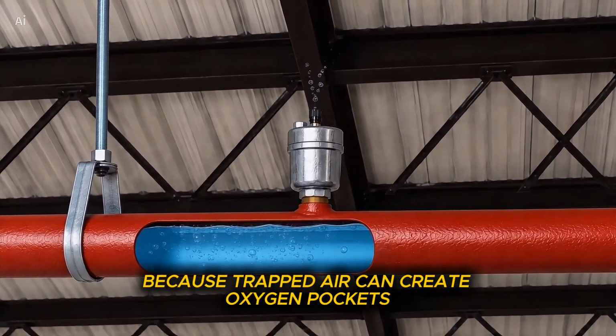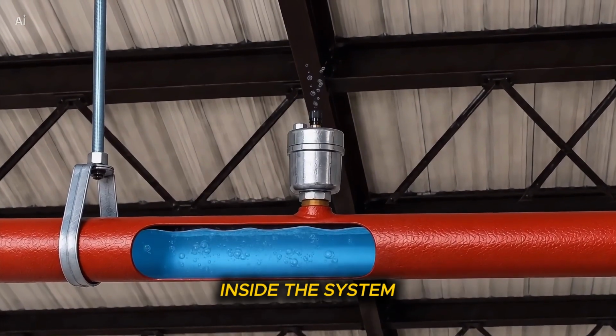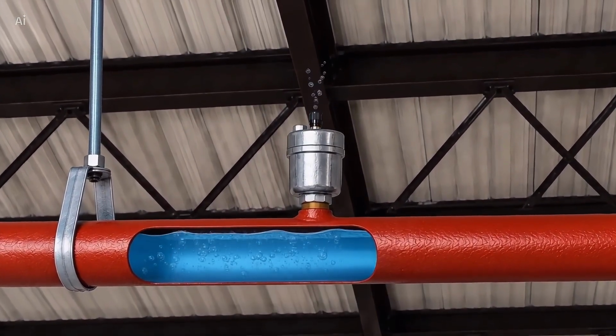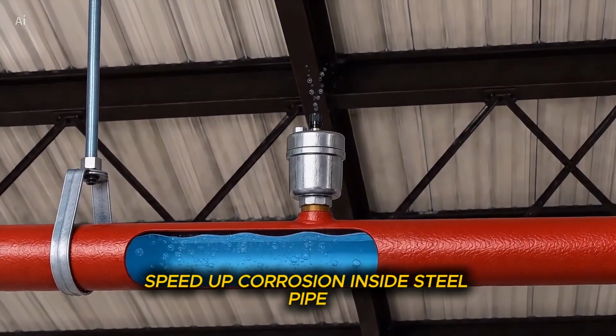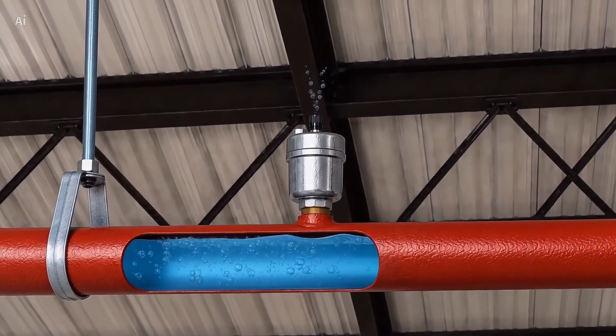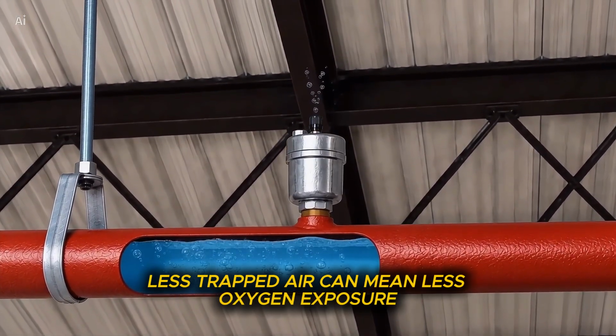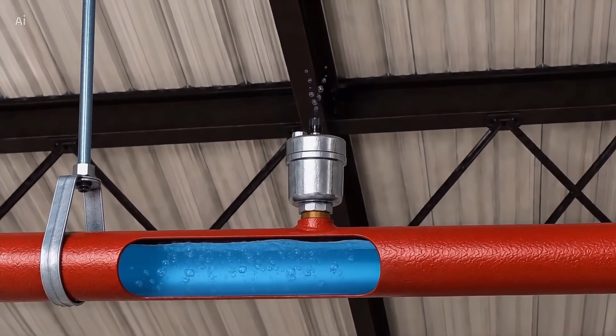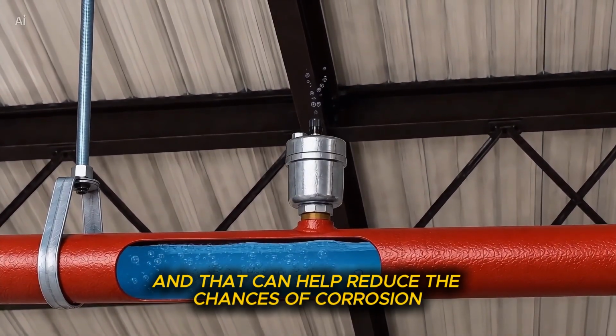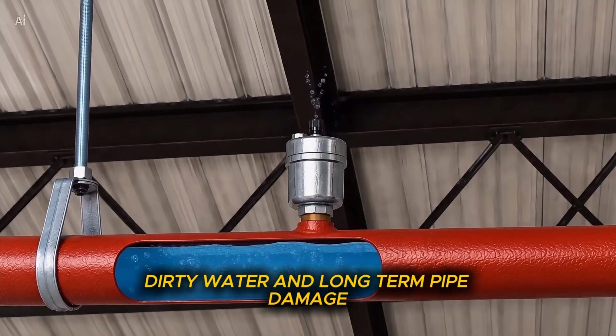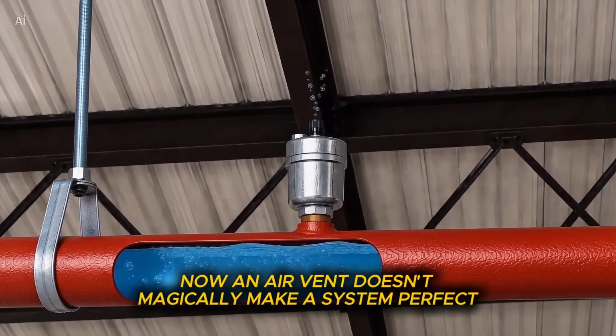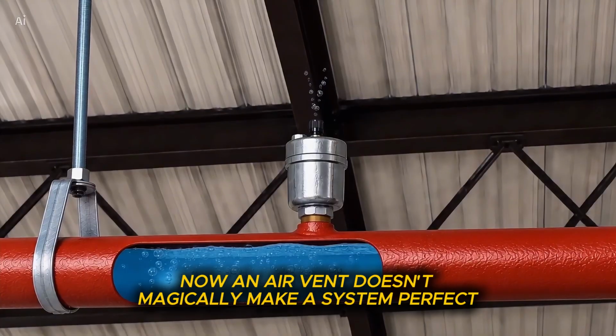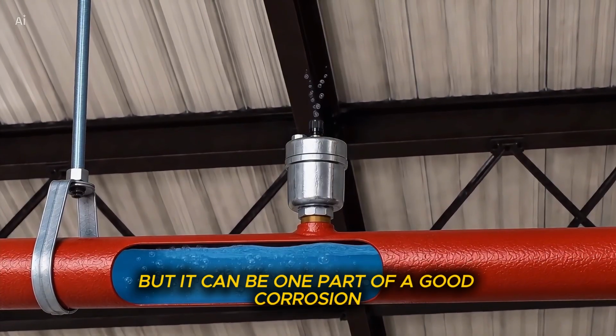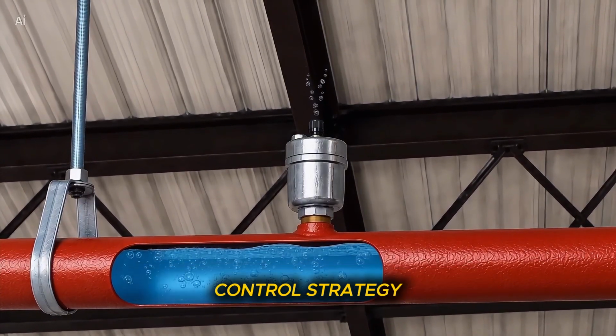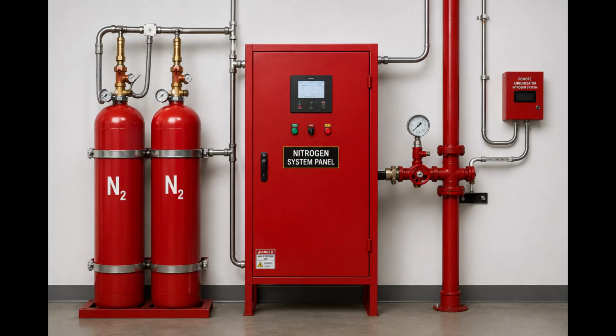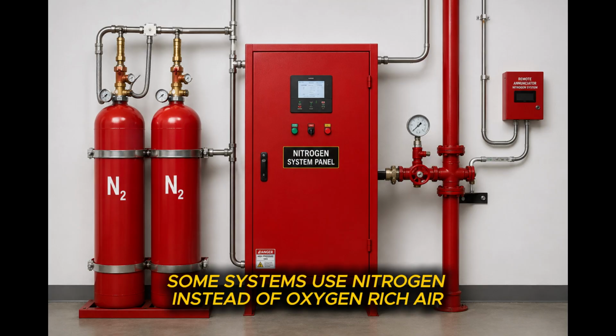This matters because trapped air can create oxygen pockets inside the system. And oxygen is one of the things that can speed up corrosion inside steel pipe. Less trapped air can mean less oxygen exposure. And that can help reduce the chances of corrosion, dirty water, and long-term pipe damage. Now, an air vent doesn't magically make a system perfect, but it can be one part of a good corrosion control strategy. Some systems use nitrogen instead of oxygen-rich air.